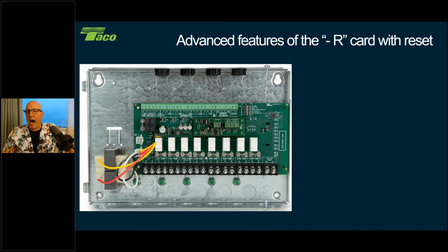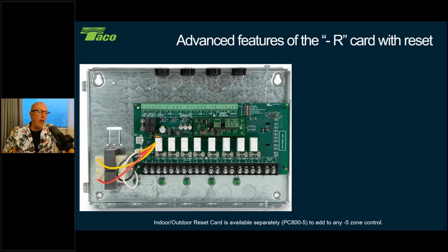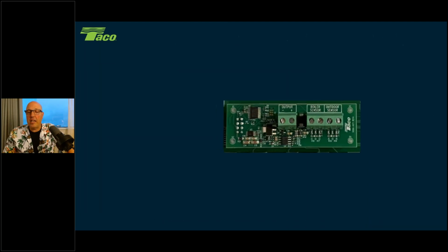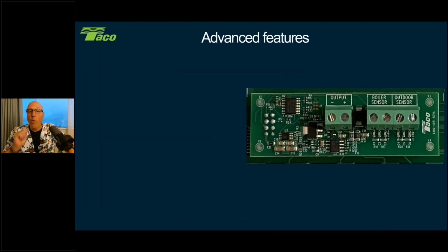All right. What else have we added to these things? Well, we have the optional -R card. So you'll see right here in the middle of this board is showing the addition of an extra circuit. All right, so we have this extra card that can snap right into the board. And it's a separate item, we call it the PC800. What that does is it gives us indoor or outdoor reset, or I like to say load compensation and weather responsive, all right. So you set it up either way.